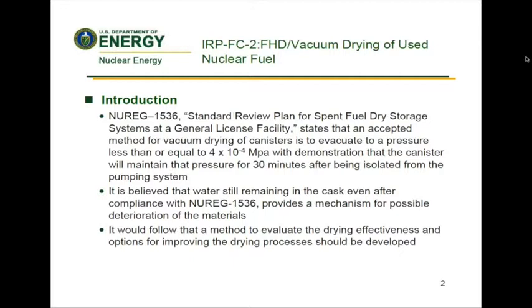NUREG-1536 Standard Review Plan for Spent Fuel Dry Storage Systems at a General License Facility states that an accepted method for vacuum drying of canisters is to evacuate to a pressure less than or equal to 4×10⁻⁴ megapascals, with demonstration that the canister will maintain that pressure for 30 minutes after being isolated from the pumping system. It is believed that water in the cask provides a mechanism for possible deterioration of the materials. It would follow that a method to evaluate the drying effectiveness and options for improving the drying processes should be developed.